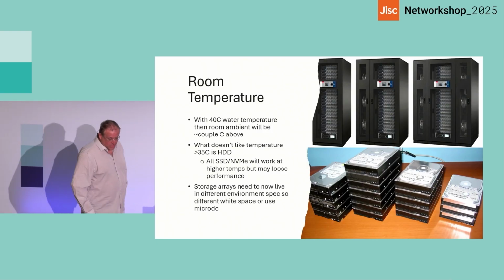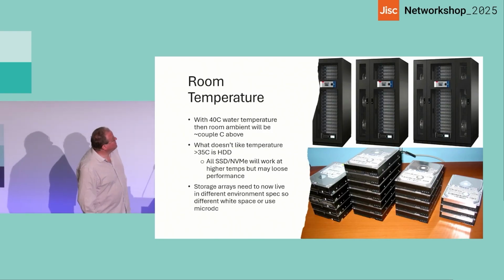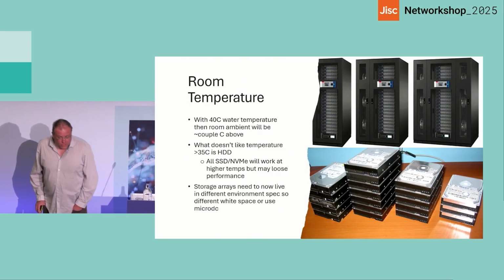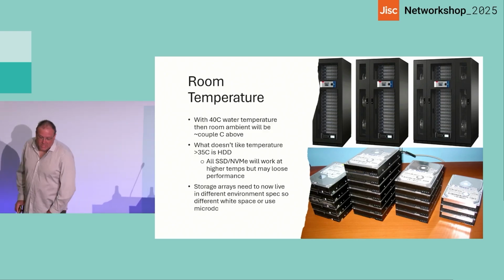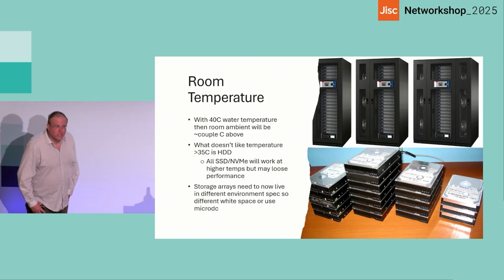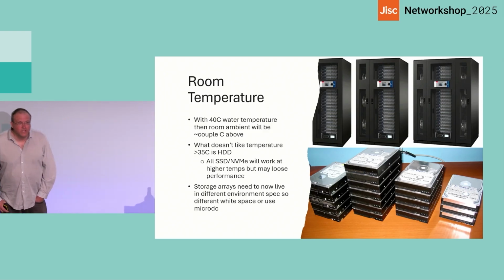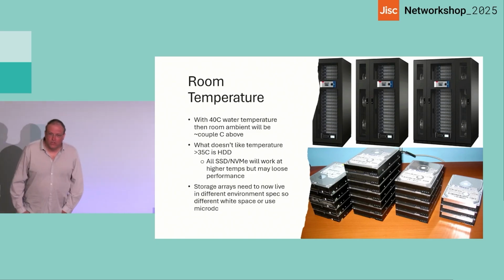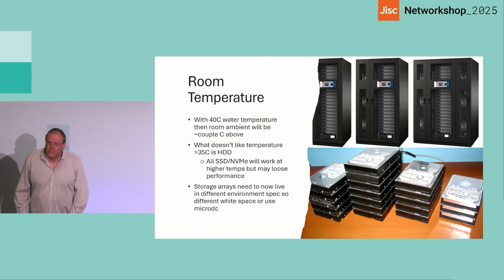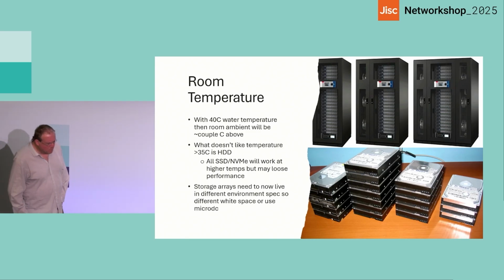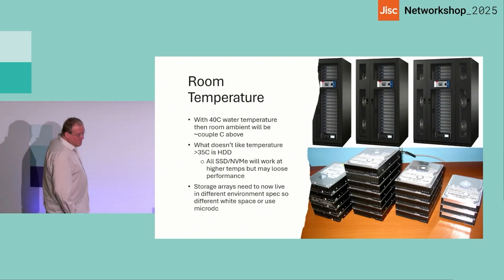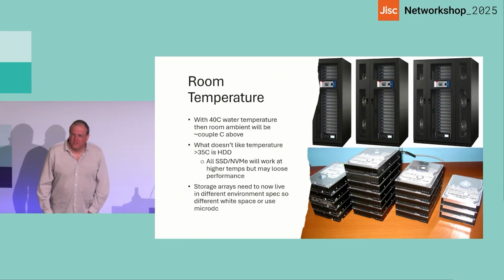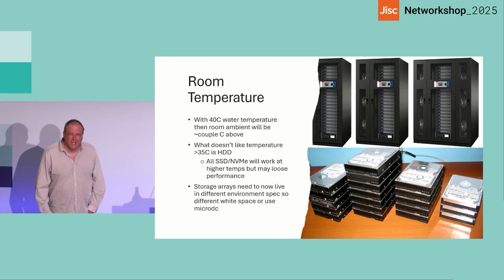So, room temperatures. As we've said, we could do a 40-degree water temperature input. Well, if your rear cooling doors at the back are getting 40 degrees of cold water in, your room is going to be 40-odd degrees warm. It's lovely if you like the tropics. Most people don't. And unfortunately, there are things called hard drives that we all still kind of use, and they really hate 40 degrees. You've got about a 35-degree limit on a hard drive.